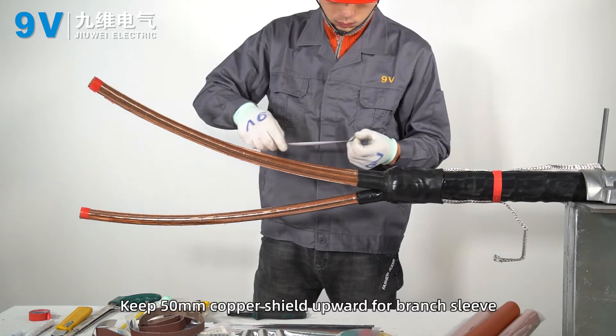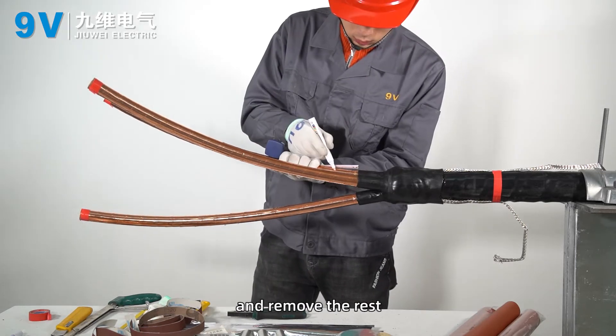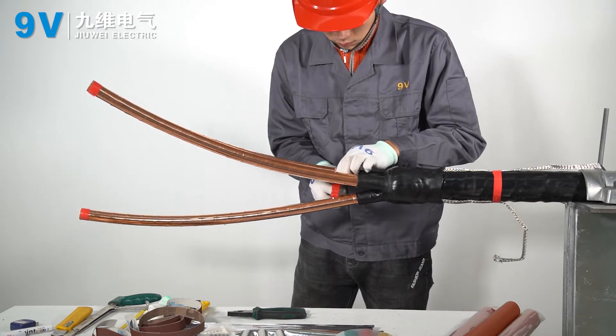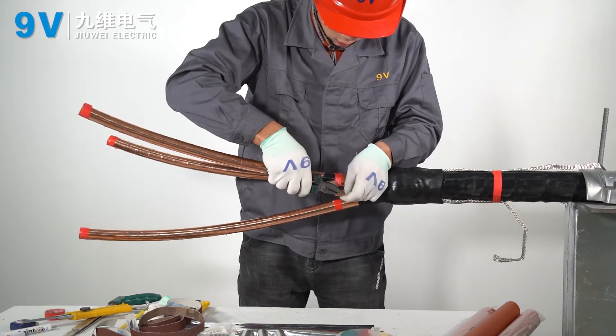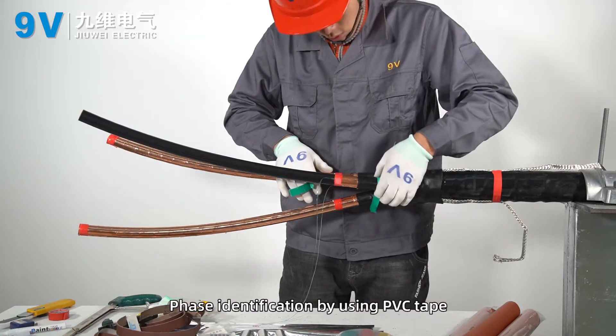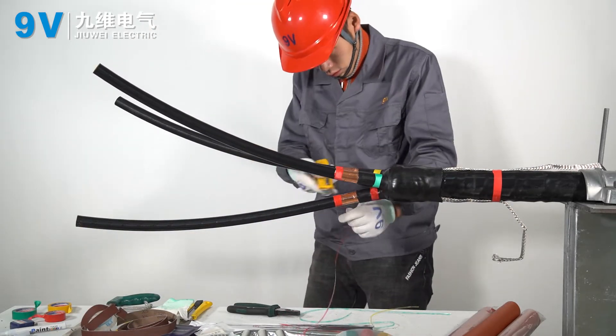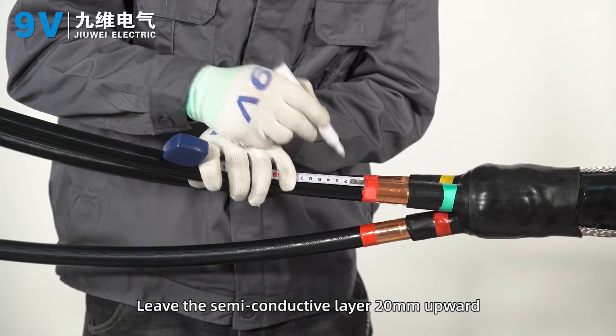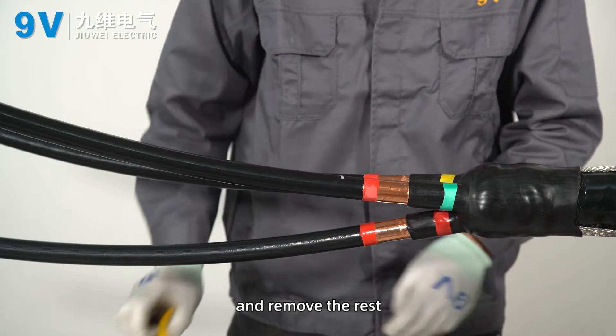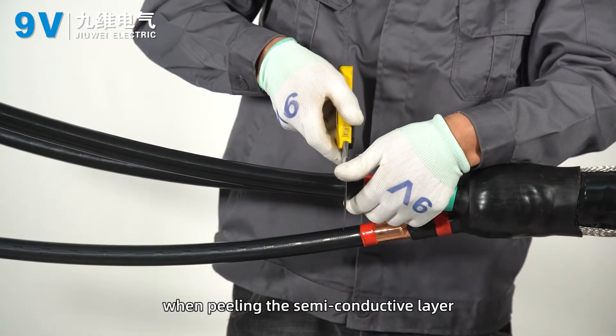Keep 50 millimeters of copper shield upward for the branch sleeve and remove the rest. Perform phase identification using PVC tape. Leave the semi-conductive layer 20 millimeters upward and remove the rest. Do not damage the main insulation layer when peeling the semi-conductive layer.